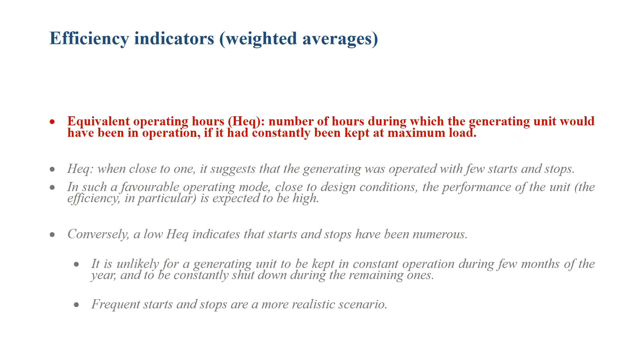In this favorable mode, the performance of the unit is expected to be high - it is easy for the unit to be performant. Conversely, a low number of equivalent operating hours indicates that starts and stops have been numerous. Of course, we might theoretically think that a unit has only had one start and one stop in a year, and then nothing else, kept out of operation for the rest of the year. But that's unlikely - when we see a low number of equivalent operating hours, the first thing we must think is that there were many starts and stops, that's a more realistic scenario.